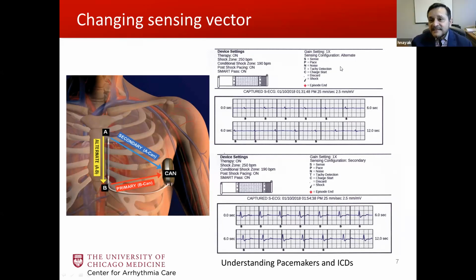So when we change the sensing vector to alternate, you can see that the electrogram, the subcutaneous signals, I should say, are a lot smaller, diminutive. And there's a concern that we may not be sensing well here. When we changed it to secondary, it was better. You can see that the electrogram amplitude was larger, but there's also a chance that it may not sense completely.